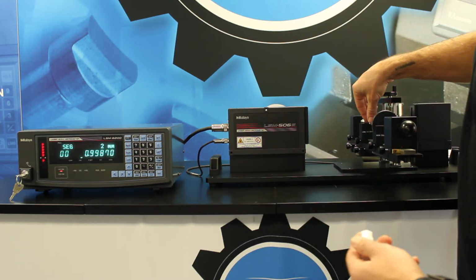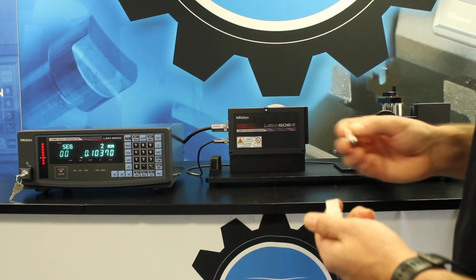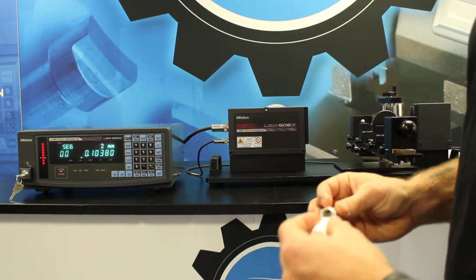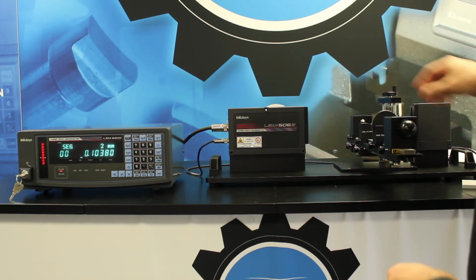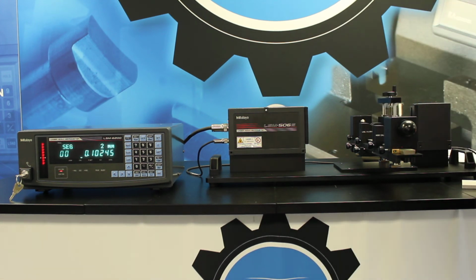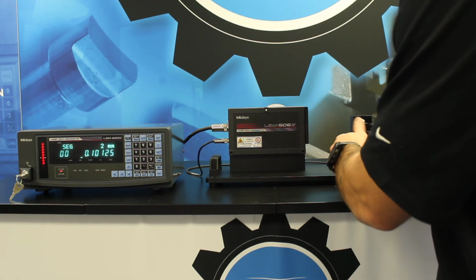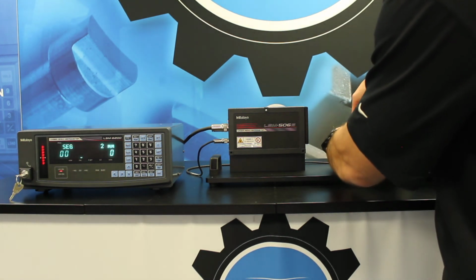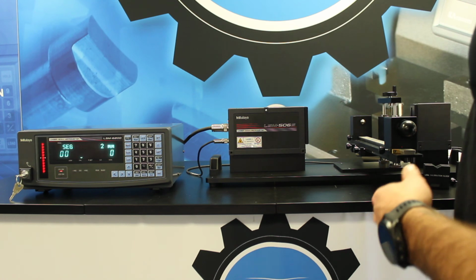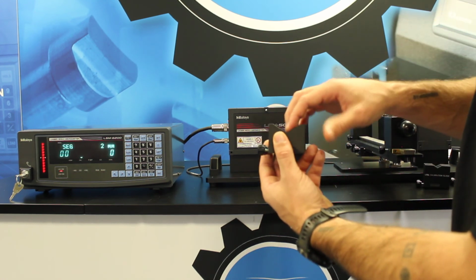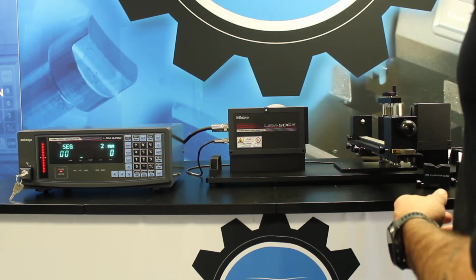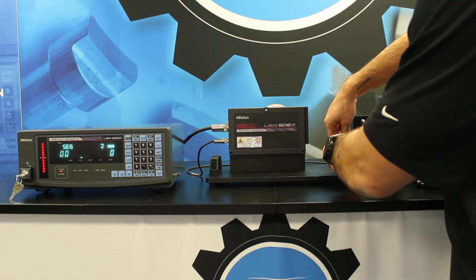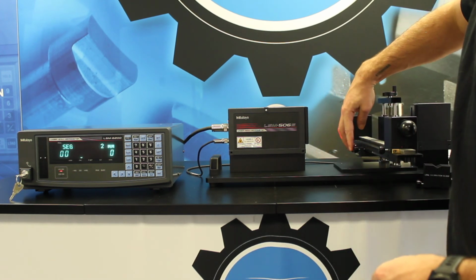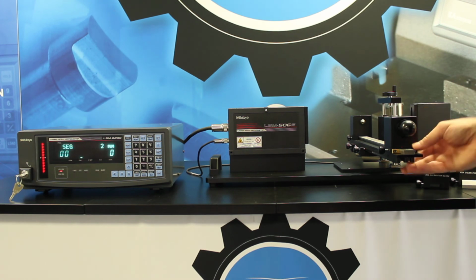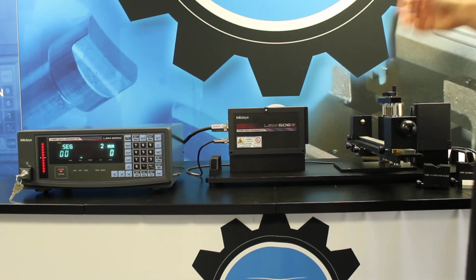At this point, the laser scan micrometer is calibrated, so I can use the thumb screws to unlock and remove my V-blocks and my artifacts. I'm going to carefully take out each artifact as to not damage or misplace those. And go ahead and remove those V-blocks. There are additional V-blocks provided if you will be using the V-blocks to locate the part. In this scenario, we are going to be using the centers. So I'm going to make sure that my thumb screws on my rail are nice and snug, so that's not going to move when I try to install my part.